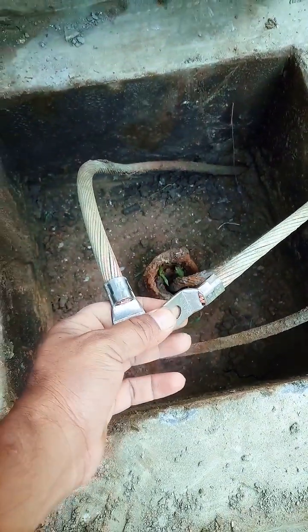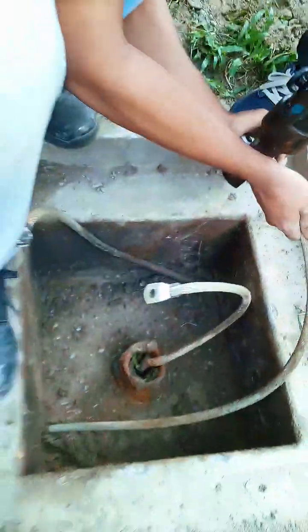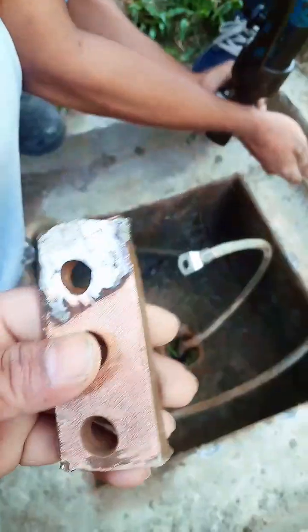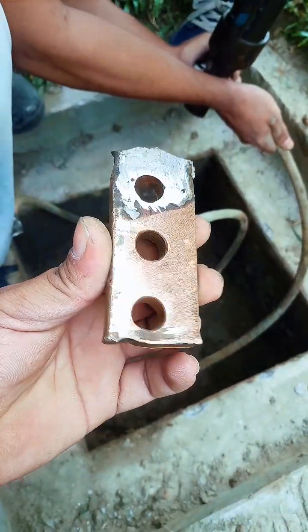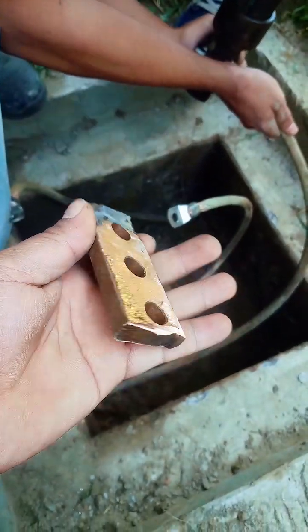We also checked the continuity from the lightning arrestor down to the earthing pit. The grounding path must be single, solid, and uninterrupted.